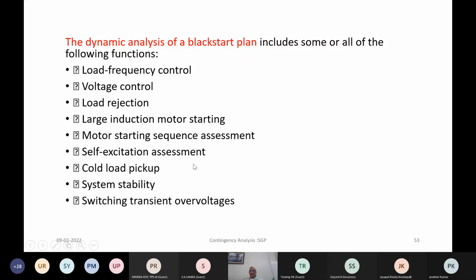Self-excitation assessment. Again, this is due to the leading reactive power being fed. The generator goes into self-excitation mode initially. Cold load pickup, system stability aspect, switching transient overvoltages. Many times you face, especially if you have got a GIS, GIS isolator operations along with the line capacitance, etc., can result in transient overvoltages, which can be dangerous. And there are cases where failures have happened during the black start mode of operation.